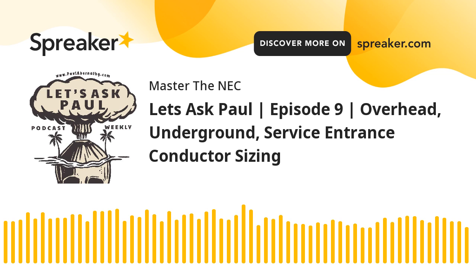When we're dealing in part 4, if you define what you're dealing with as service entrance conductors, then we have to look at something different here. And it says, service entrance conductors shall have an ampacity, again, not less than the maximum load to be served. So you do a calculation, whatever that calculation is, that is the load to be served, and you make sure you size your conductors accordingly.